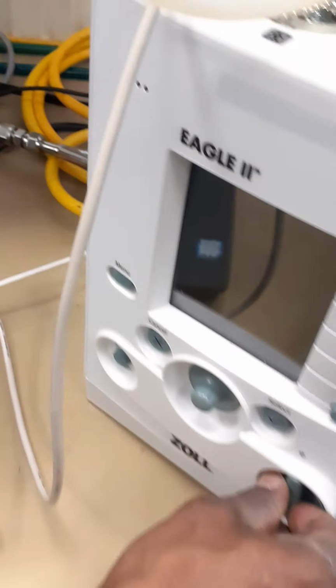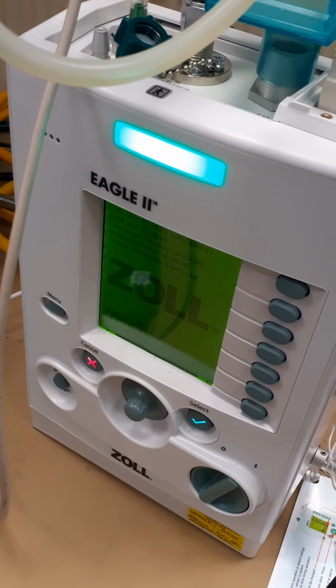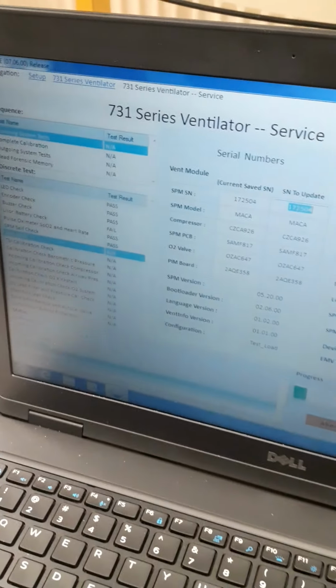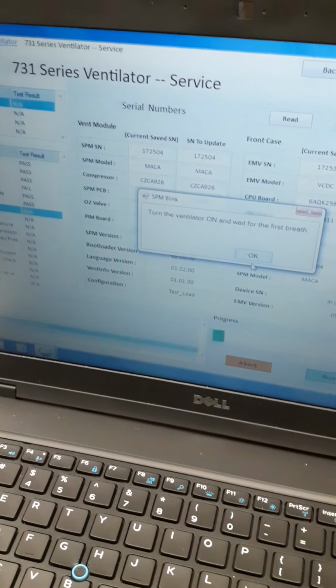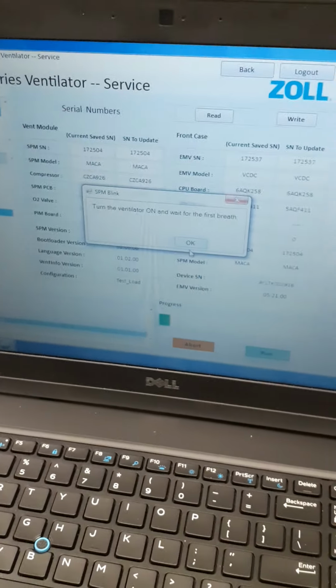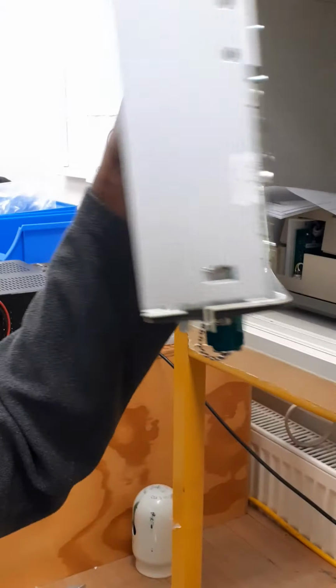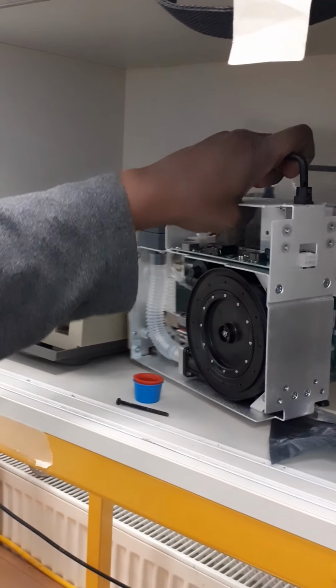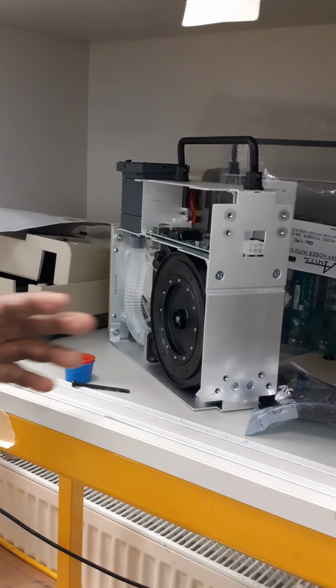Alright, so turn on the ventilator and wait for the first breath. That's the first breath. Turn it back off. SPM, so that's the pneumatic module, it's checking. I'll show you what that module is. This is your SPM. So that's the self-check. This is the heart of the unit. That's your compressor and everything attached to it. Okay.